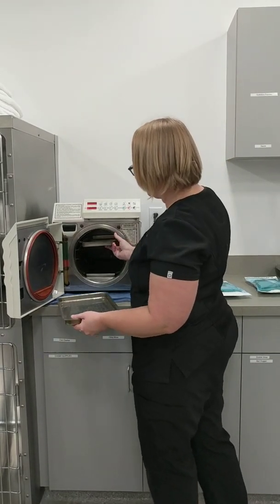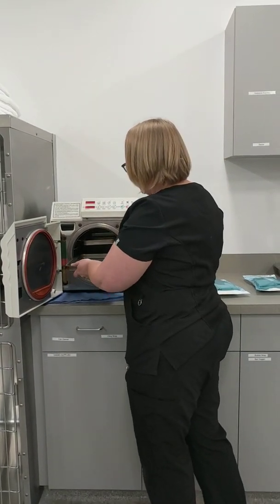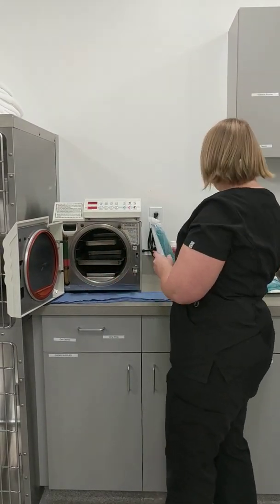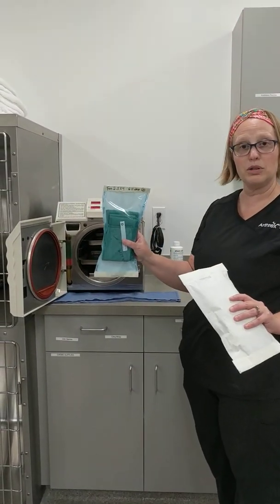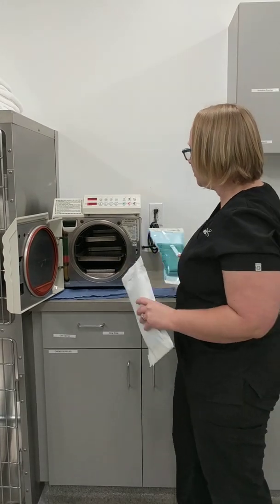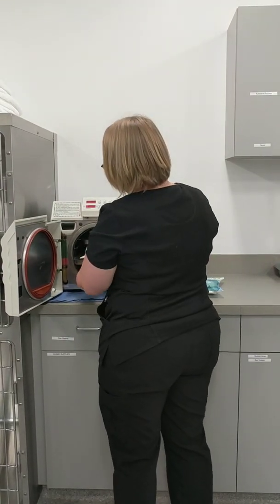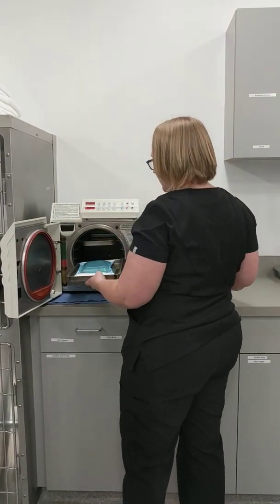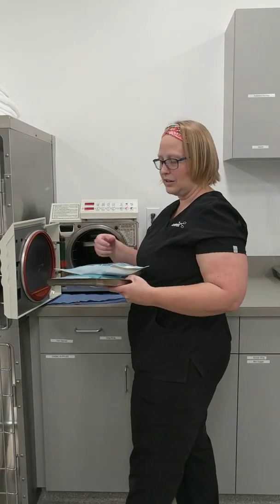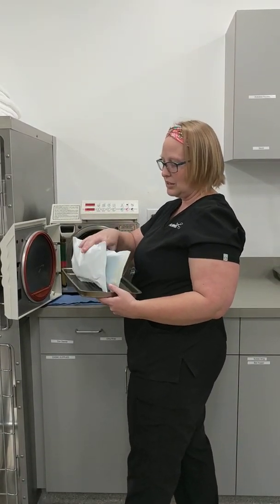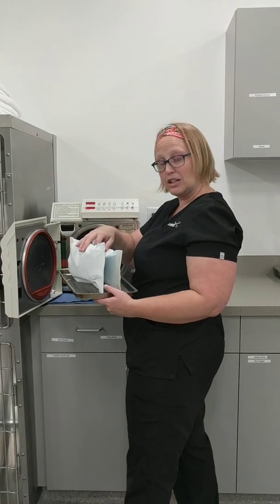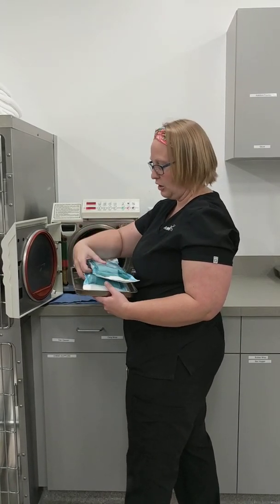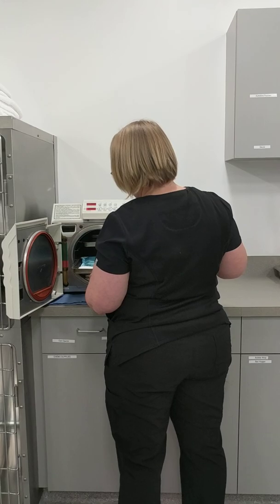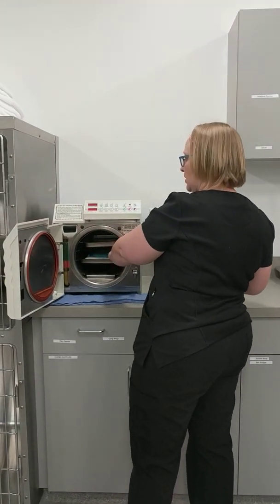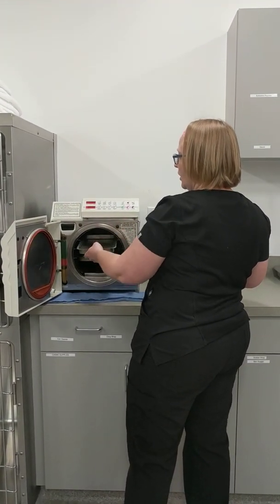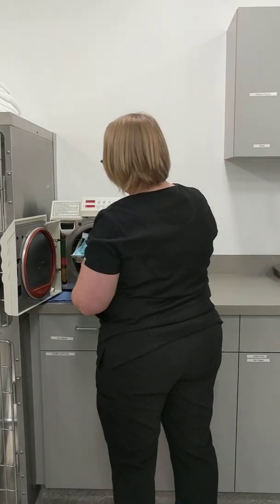So first, what we're going to demonstrate today is, again, pouch settings. I have 2 pouches already prepped and ready for sterilization. They're both labeled. One thing you need to understand is that you aren't going to stack these like this. That's not a good position. Doing it like this, as long as you have spacers, might be acceptable, but it's not standard of care. So we're going to go with 1 tray layer here. I'm skipping my middle tray here to allow more airflow and putting my second one on the top.